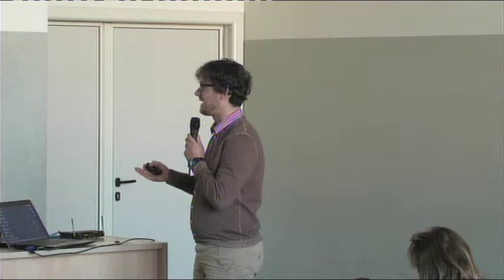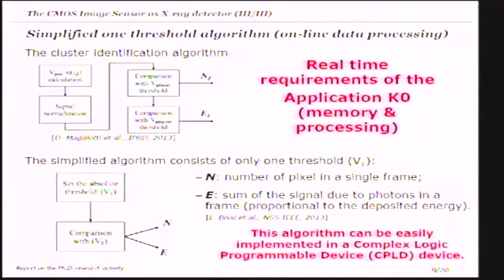The algorithm is not compatible with the real-time and low power requirements of the system. Therefore, a simplified algorithm was developed that consists of just one threshold. We compare an absolute threshold with the raw data of the pixel. The two new observables are the number of pixels above threshold in a frame and the sum of the signals of the pixels above threshold in a frame. These two observables are still correlated to the dosimetric quantities, and the performances of the two algorithms are the same — so we don't lose information by using these two new observables.